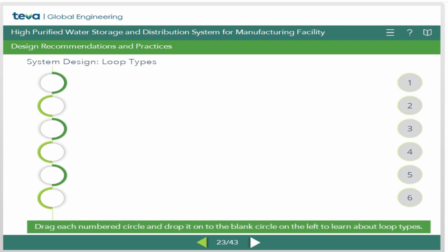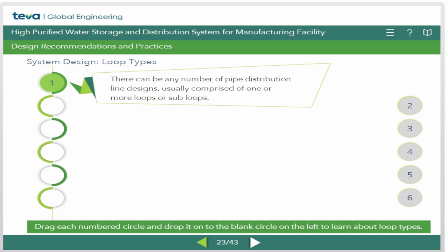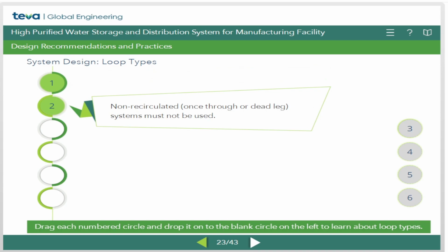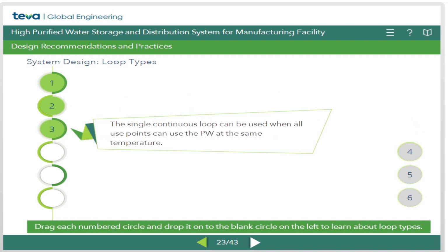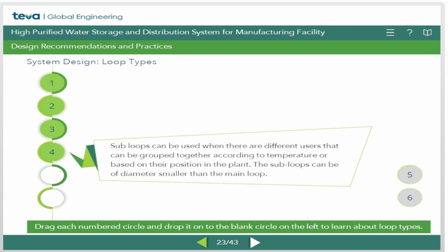Drag each numbered circle and drop it onto the blank circle on the left to learn about loop types. There can be any number of pipe distribution line designs, usually comprised of one or more loops or subloops. Non-recirculated systems must not be used. The single continuous loop can be used when all use points can use the purified water at the same temperature. Subloops can be used when there are different users that can be grouped together according to temperature or based on their position in the plant.